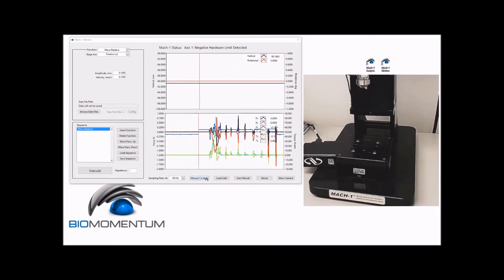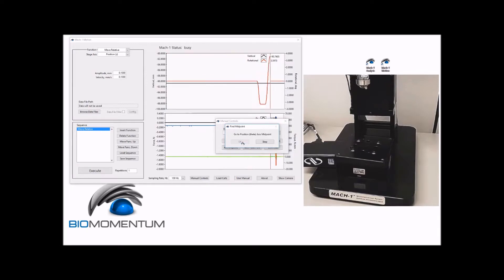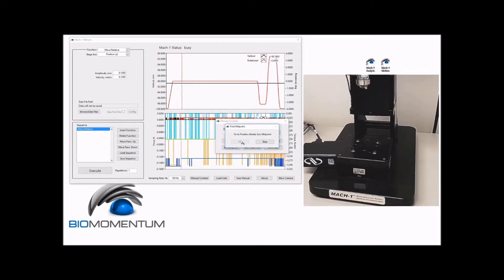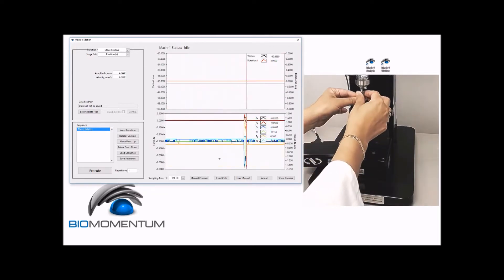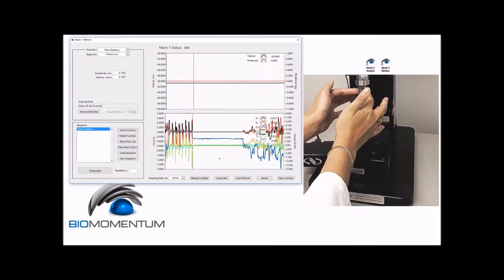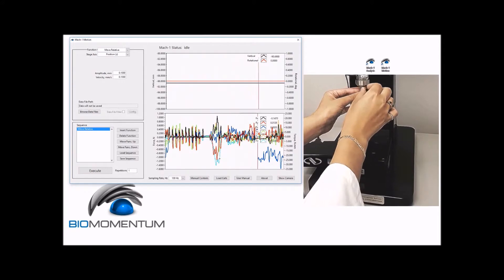Open the manual controls window and set the axis to position theta. Set the rotational stage to its midpoint using the axis midpoint button. Then gently screw the flat indenter under the load cell and lightly finger tighten to secure it.